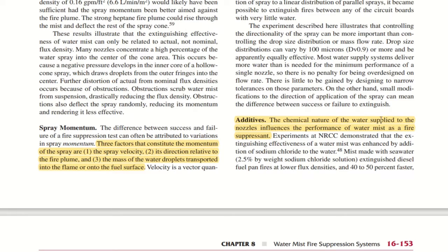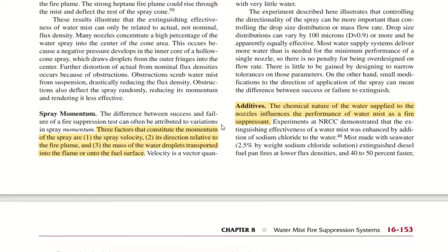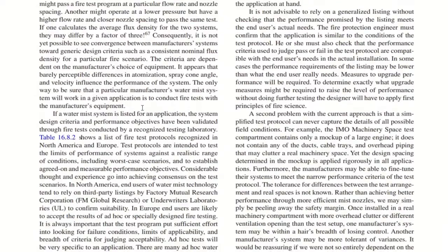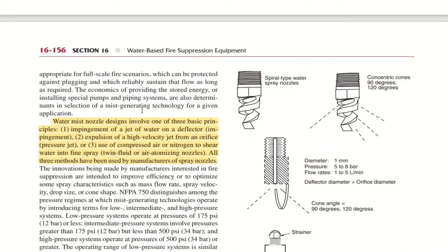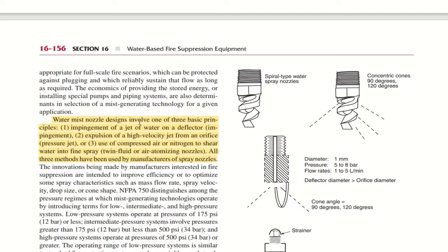Additives. The chemical nature of the water supplied to the nozzles influences the performance of water mist as a fire suppression agent. So for the design of water mist systems, there are several points to be reviewed. Water mist nozzle design involves one of three basic principles: impingement of a jet of water on a deflector, expulsion of a high velocity jet from an orifice, or use of compressed air or nitrogen to shear water into fine spray. All three methods have been used by manufacturers of spray nozzles.